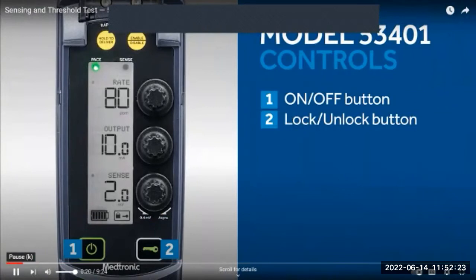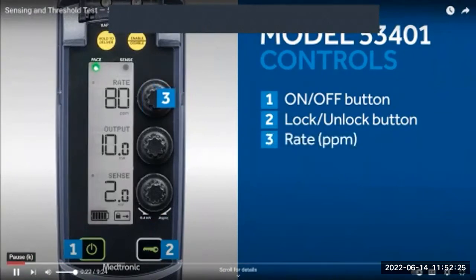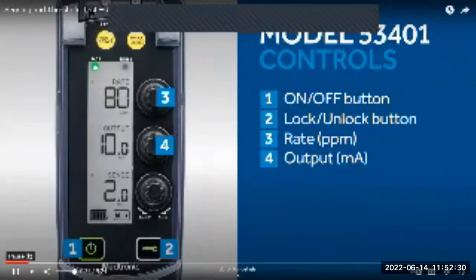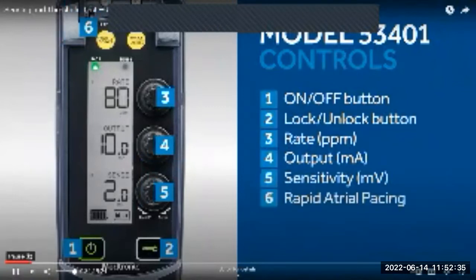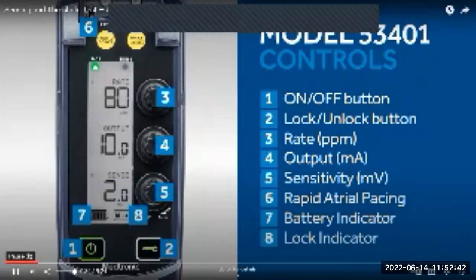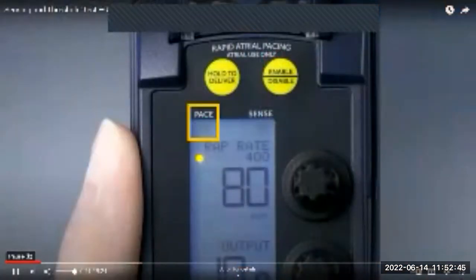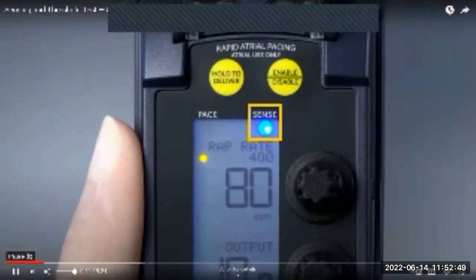The on-off button is located here. This is the lock-unlock button. Pacing rate is adjusted using this dial. This is the dial to adjust the pacing output in milliamps. This is the dial to adjust sensitivity in millivolts. These are the controls for rapid atrial pacing. This is the battery indicator. This is the lock indicator. This is the green light, which indicates pacing when flashing. This is the blue light, which indicates sensing when flashing.